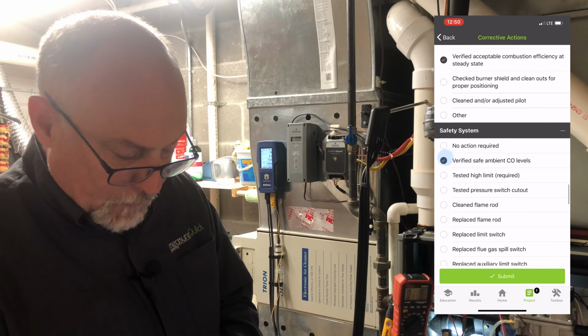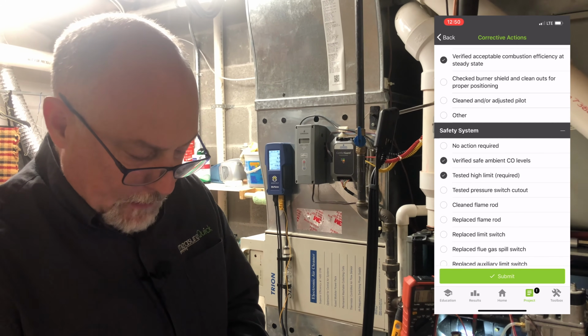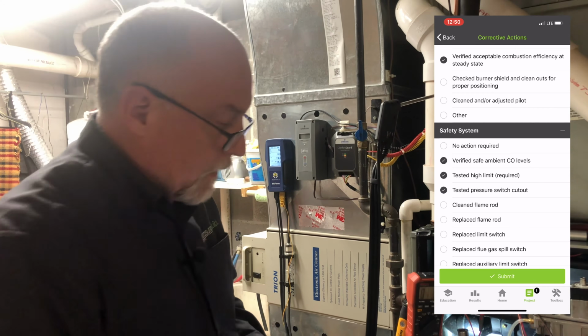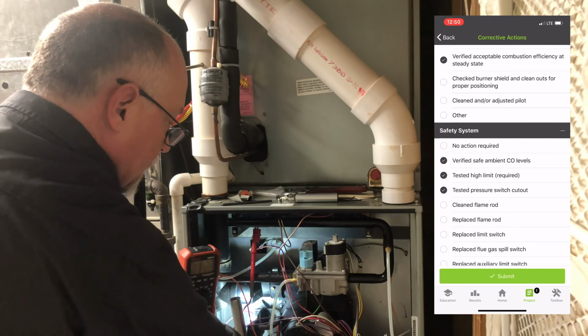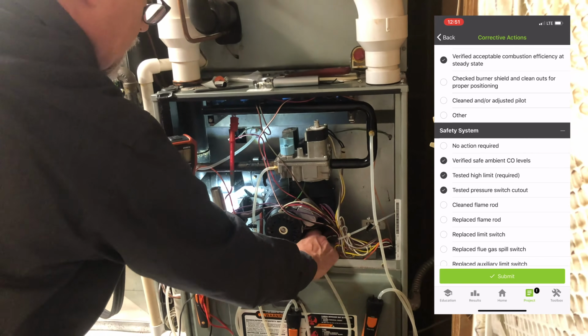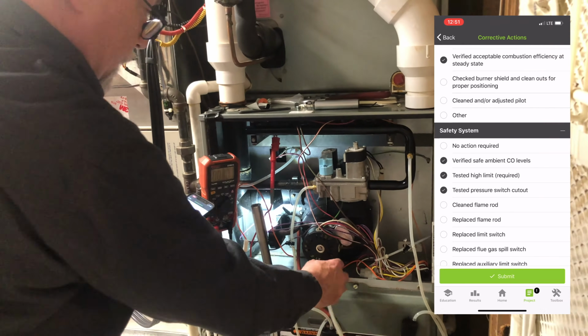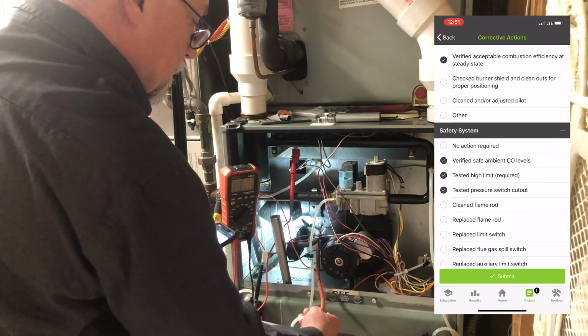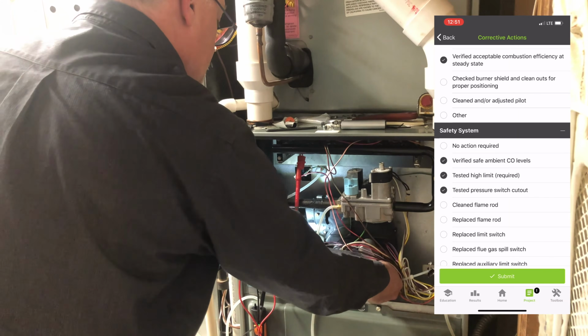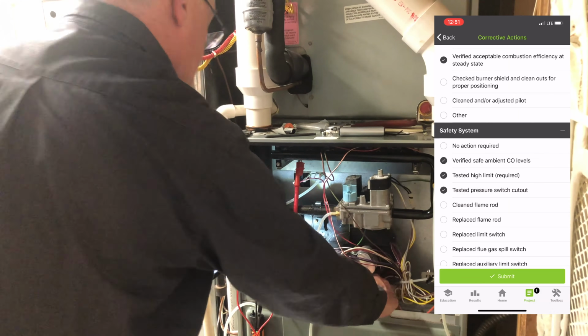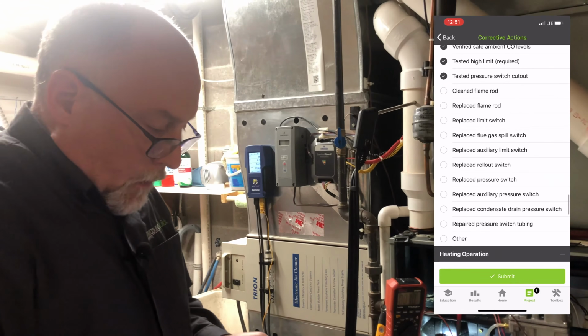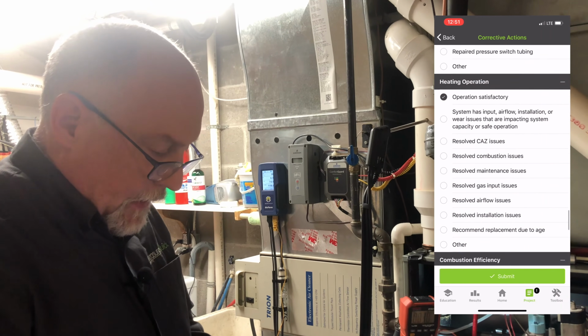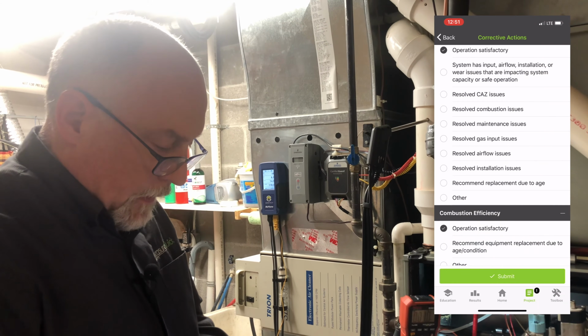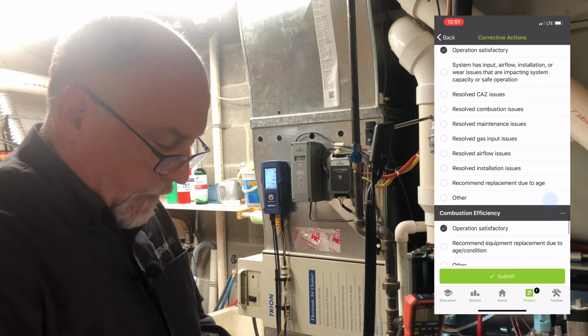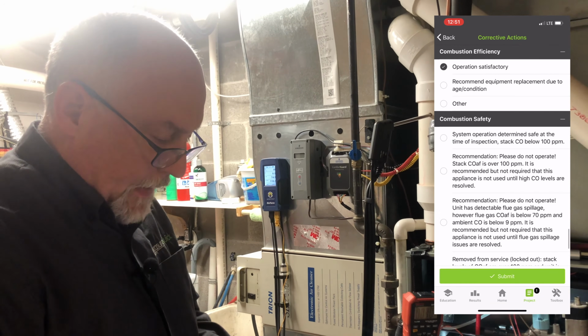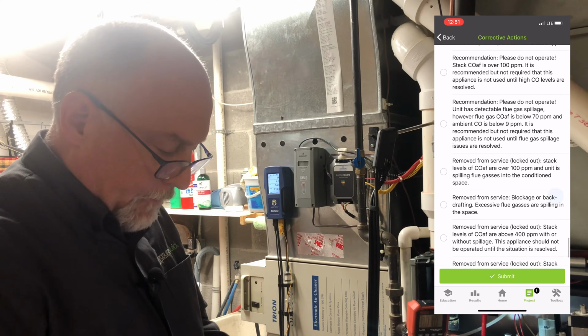And then our safety system, we verified our ambient CO levels and tested our high limit. Tested our pressure switch cutout, which we can just test to make sure the switch cuts out. You can just disconnect it here. And so that does cut out. We'll go ahead and reconnect our switch. All right. We did clean the flame rod earlier. This heating operation is good. No issues to resolve on here. Operation satisfactory. The CO is below 100 parts per million. And we're good to go.